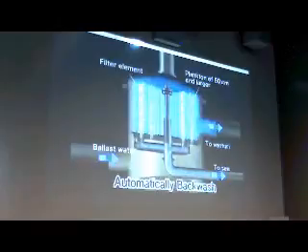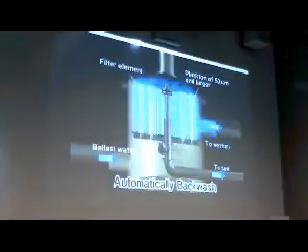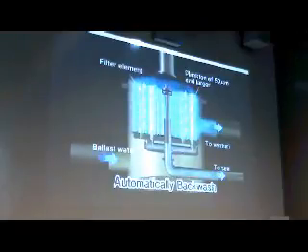Treatment of ballast water taken on by the ship begins with the filter system. The ballast water enters the filters from the bottom, and plankton with sizes of 50 microns and larger are removed by the filter elements. Filter elements are automatically backwashed in sequence. The removed plankton are returned to the sea together with the ballast water. During backwashing, the other filters continue treatment.